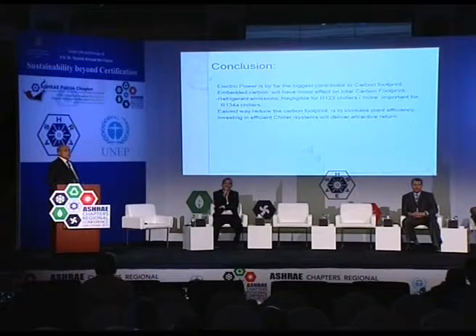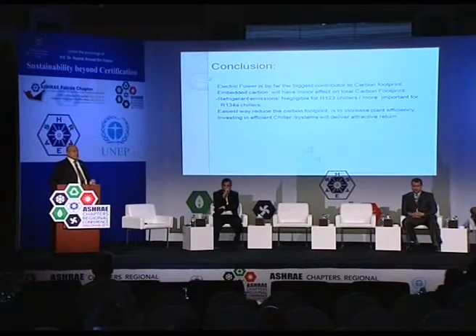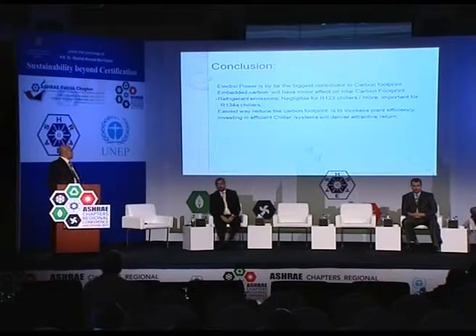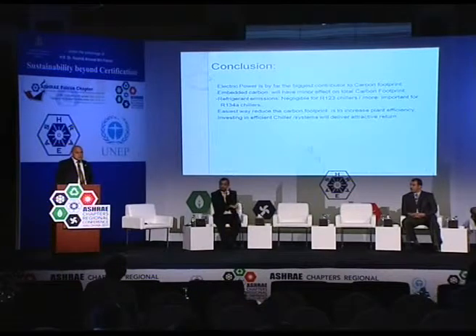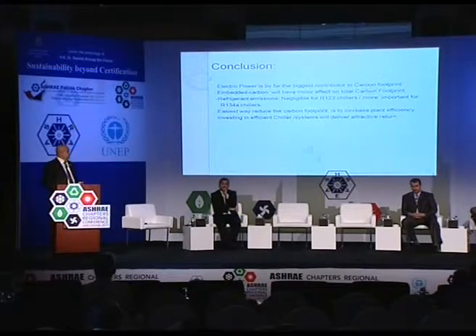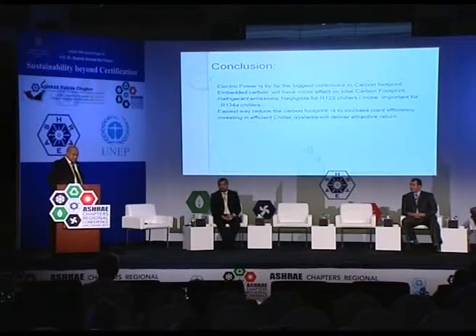So, in conclusion, for district cooling plants, don't waste too much time. Electric power is the biggest contributor, more than 90% whatever happens. The embedded carbon is very negligible, around 0.2%. The refrigerant emissions are negligible for R123, more important for R134A, noting that everybody should be responsible these days and contain the refrigerant in the plant. So concentrate on plant efficiency, and investing in efficient systems will deliver a good return.